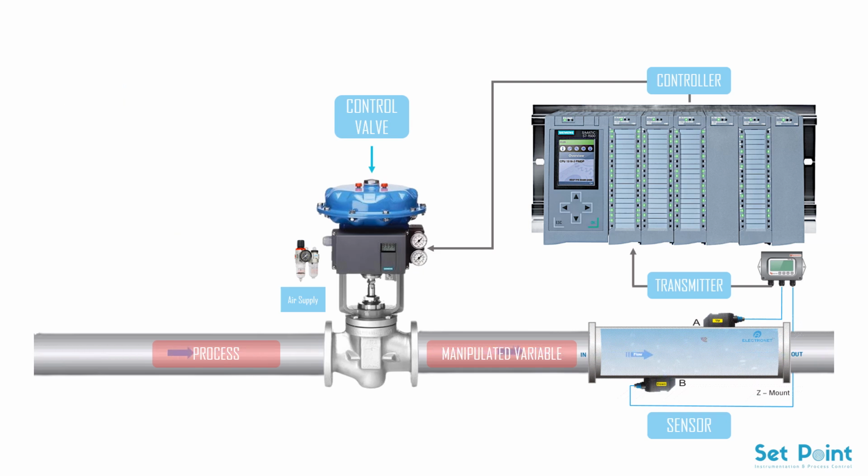In most applications, a control valve is the final element in the classic control loop. It provides the necessary power to translate the controller's output to process either two positions, on, off, or proportional throttling. Of the three basic components of a typical loop, sensor, controller, and valve, the valve is subject to the harshest condition and is the least understood. To complicate matters, the valve is also the most expensive and most prone to incorrect selection.